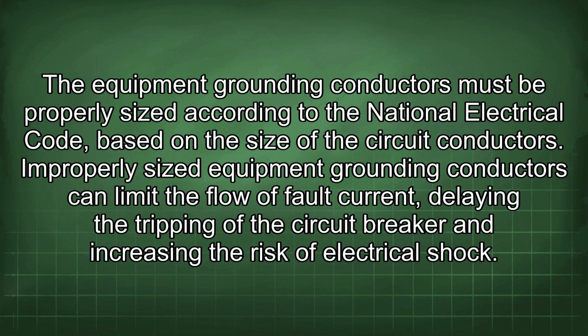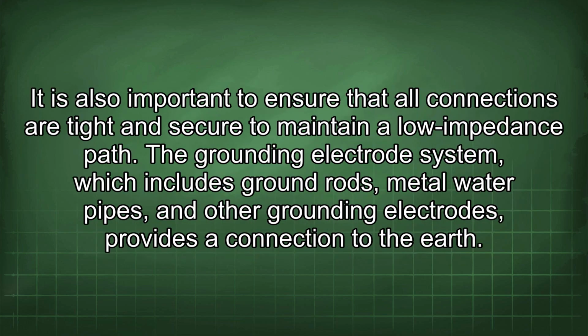The equipment grounding conductors must be properly sized according to the National Electrical Code, based on the size of the circuit conductors. Improperly sized equipment grounding conductors can limit the flow of fault current, delaying the tripping of the circuit breaker and increasing the risk of electrical shock. It is also important to ensure that all connections are tight and secure to maintain a low impedance path.